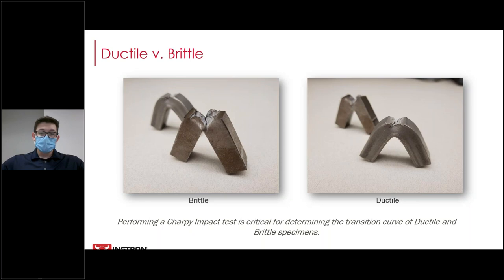So why is that exercise important? And this is depending mostly on the standard, but it's likely that the operator testing impact will need to determine this type of failure visually. And this is a very important result in your impact testing. ASTM E23 indicates that the fracture type is to be visually analyzed and recorded as a percentage value.